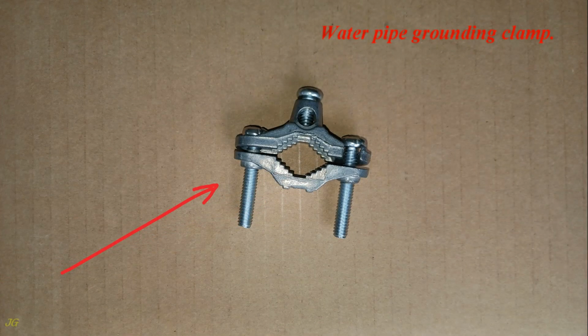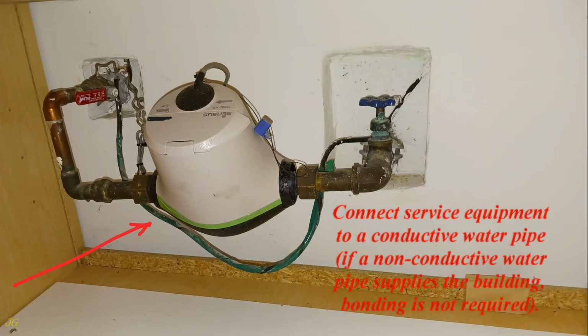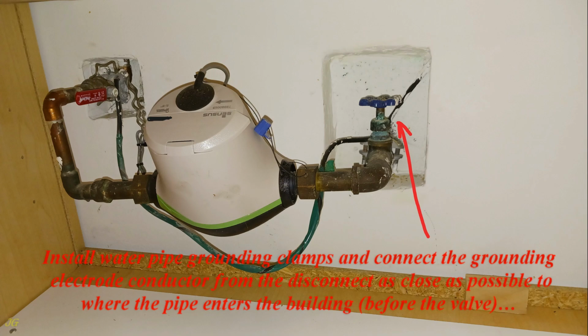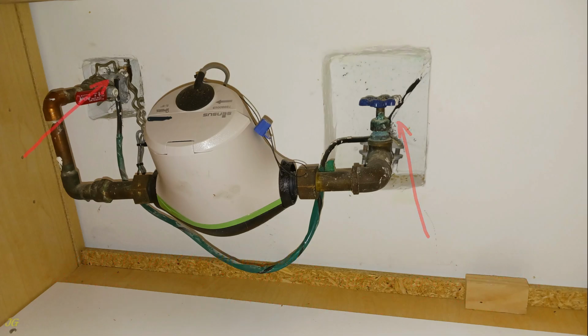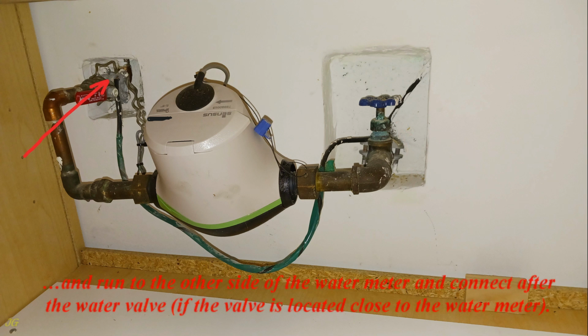Water pipe grounding clamp. Connect service equipment to a conductive water pipe. If a non-conductive water pipe supplies the building, bonding is not required. Install water pipe grounding clamps and connect the grounding electrode conductor from the disconnect as close as possible to where the pipe enters the building, before the valve, and run to the other side of the water meter and connect after the water valve, if the valve is located close to the water meter.